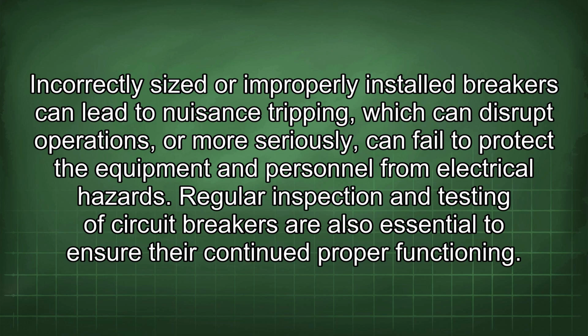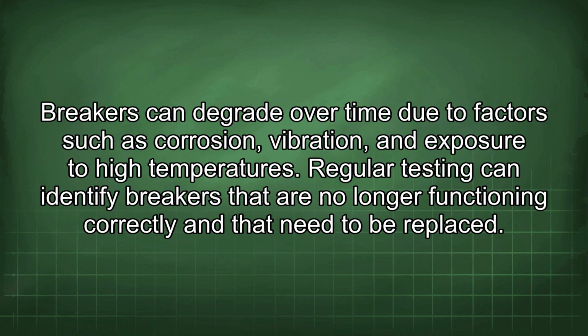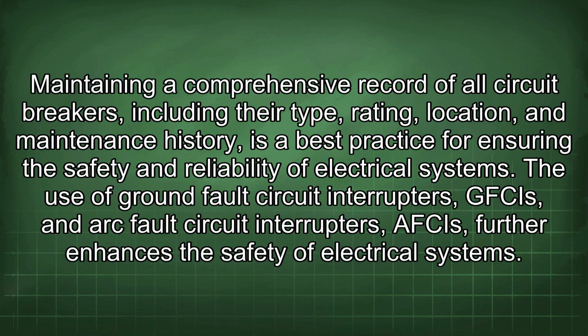Regular inspection and testing of circuit breakers are also essential to ensure their continued proper functioning. Breakers can degrade over time due to factors such as corrosion, vibration, and exposure to high temperatures. Regular testing can identify breakers that are no longer functioning correctly and that need to be replaced. Maintaining a comprehensive record of all circuit breakers, including their type, rating, location, and maintenance history, is a best practice for ensuring the safety and reliability of electrical systems. The use of ground fault circuit interrupters, GFCIs, and arc fault circuit interrupters further enhances the safety of electrical systems.